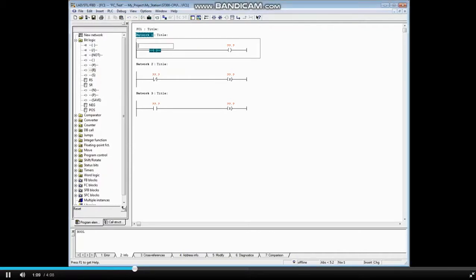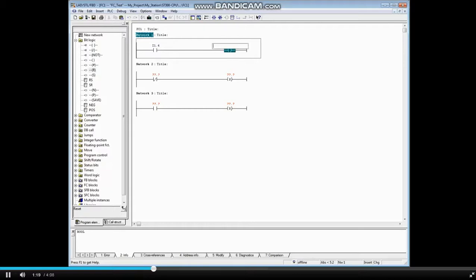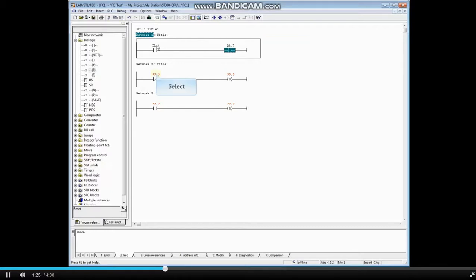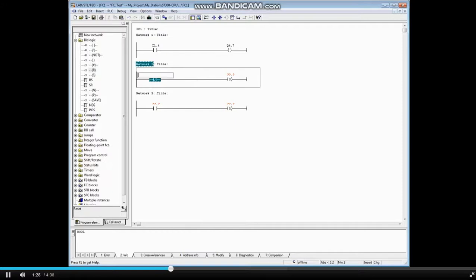We will make the first one be input I 1.4. Press the Enter key to move the highlight to the next element — in this case, the assignment coil. The assignment coil address will be Q 4.7. Press Enter. Select the normally closed contact in network 2 and assign the address I 1.5, then press Enter.